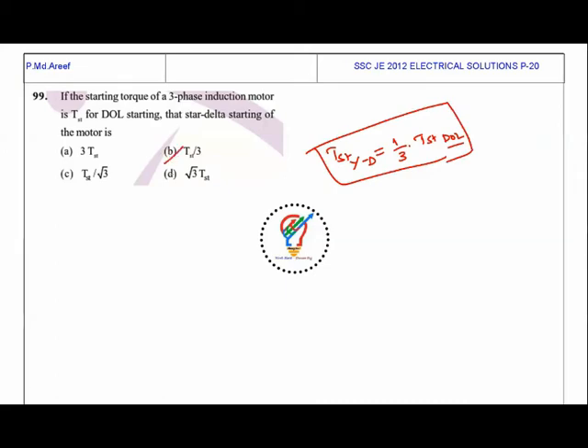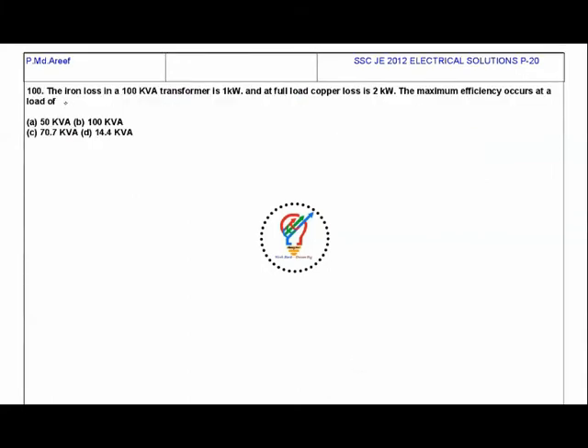Next question: the iron losses in a 100 kVA transformer is 1 kilowatt and full load copper losses is 2 kilowatts. The maximum efficiency occurs at a load of kVA at which efficiency maximum occurs is equal to kVA full load into square root of iron losses by copper losses.